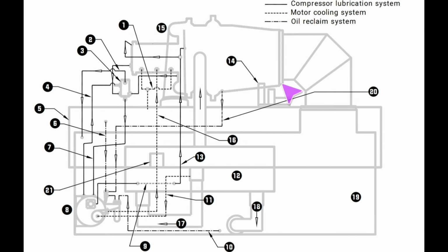One of the things that I have not discussed, and this is number 14 here, is the purge assembly. This purge assembly's job is, because again, these are low pressure machines. R11 and 123 are low pressure. They operate inside of a vacuum. They are not positive pressure or high pressure machines like 134, R22, 410A, and so on. Because they operate in a vacuum, they allow a lot of atmosphere to seep its way into the system.